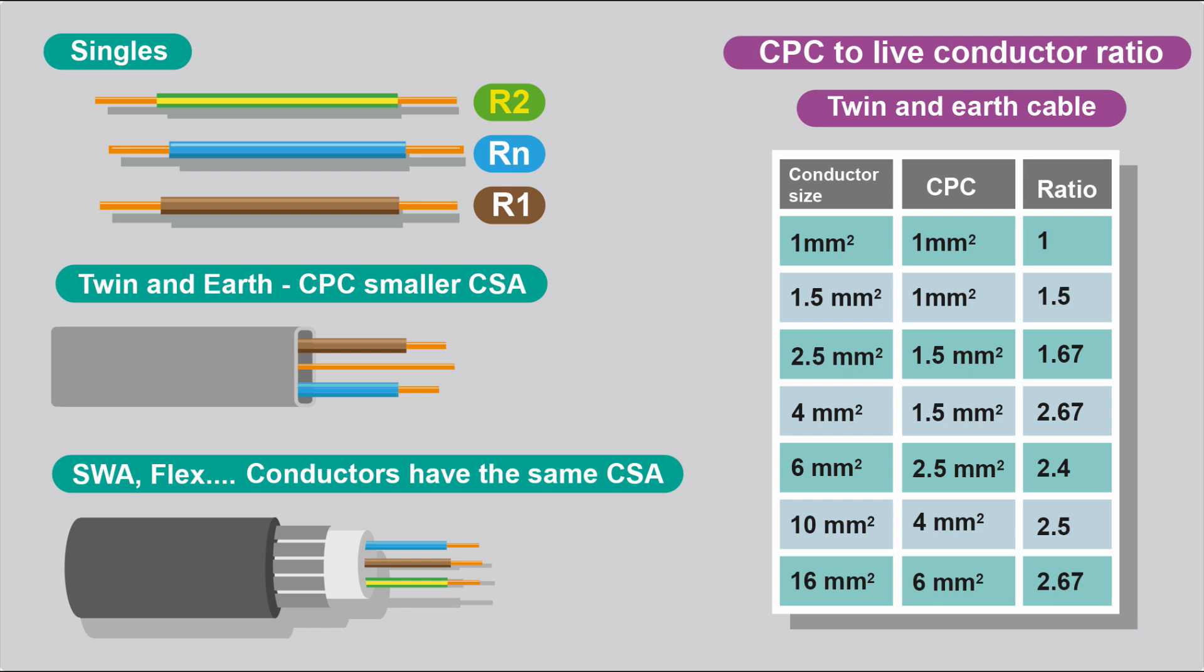On the table here, you can see it. Generally, 1mm² cable has a 1mm CPC, 1.5mm has a 1mm, 2.5mm has a 1.5mm, 4mm has a 1.5mm² CPC, 6 is a 2.5mm.